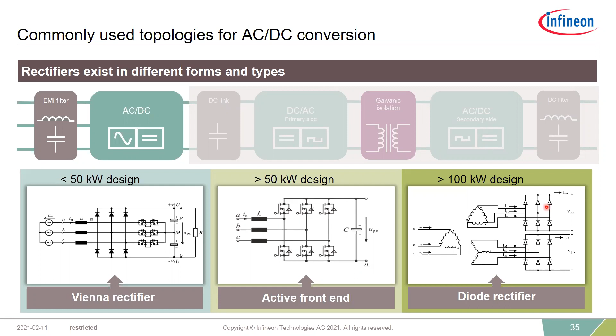If the power level goes beyond 100 kilowatt design, you need to have your own transformer. In that case, isolation is done at the input level. Then you can have two secondary windings, star and delta. By this, you can have a 30-degree phase shift, and by connecting them either in series or parallel you can compensate the THD, and also compensate the ripple component coming out of it. So generally, a bridge rectifier configuration is good enough.